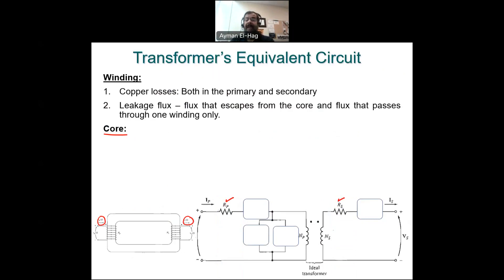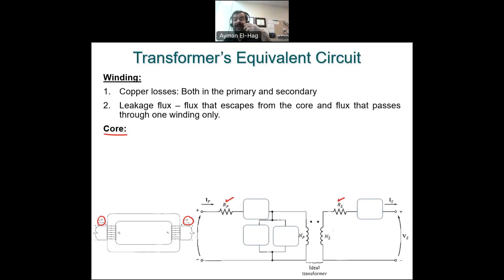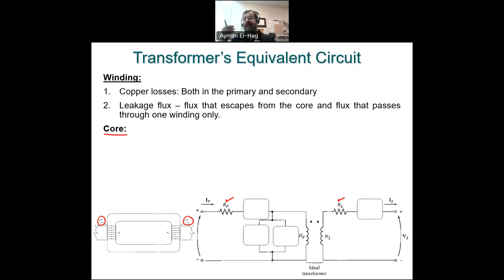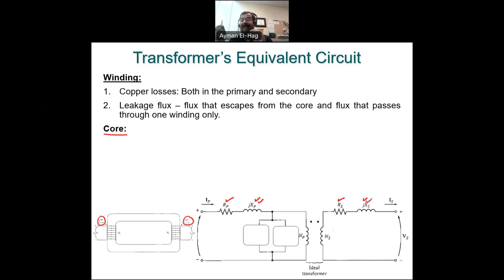Second, as mentioned previously, not all flux produced in the primary will make it to the secondary — there will be leakage on both the primary side and the secondary side. A leakage is a flux, and a loss of flux is a loss of reactive power. The best way to represent a loss in reactive power is by having an inductor. So we will have an inductor in the primary and in the secondary that represents the leakage flux.